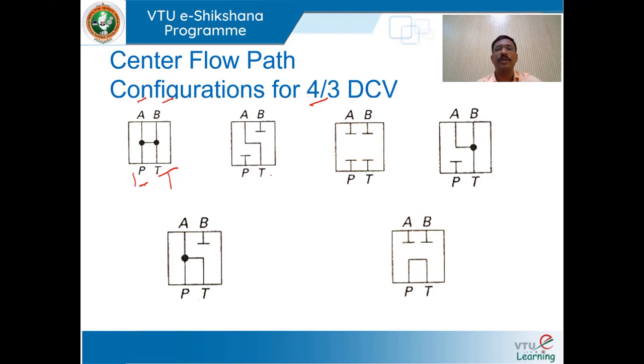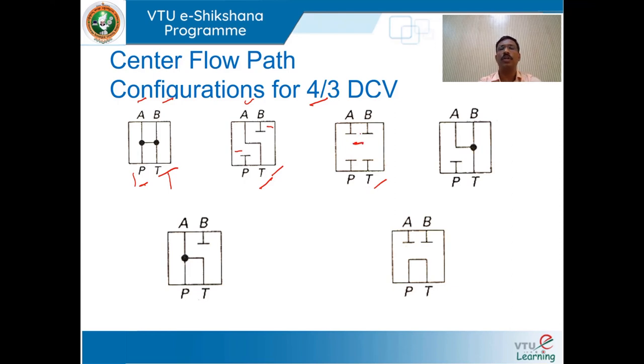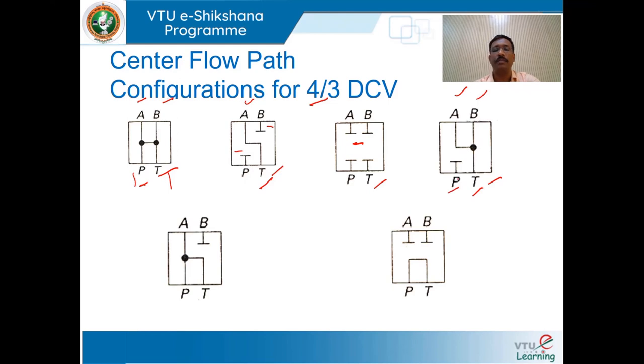In another center path configuration, port A is open to tank while ports P and B are blocked. In another configuration, all ports are closed. In yet another, A and B are open to the tank line but port P is blocked.